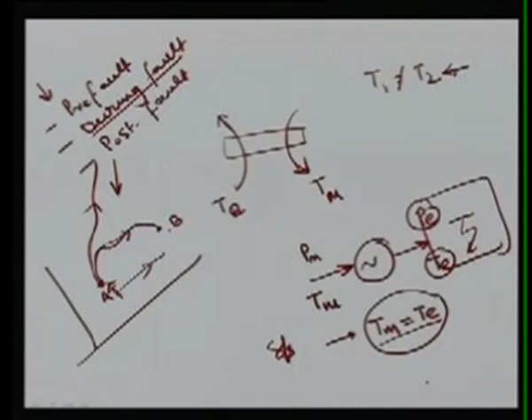So, the rotor angle instability can be categorized into two based on large or smaller disturbance: small signal stability, or we will see the transient stability. There are two types of rotor angle instability. One is your small signal stability. Basically in this we analyze with small disturbances. A small disturbance is nothing but a change in your load and change in generation. This is small, but it is always happening in the power system, because the load keeps on changing and generation is following that. So we have to analyze the behavior of the system with these changes.